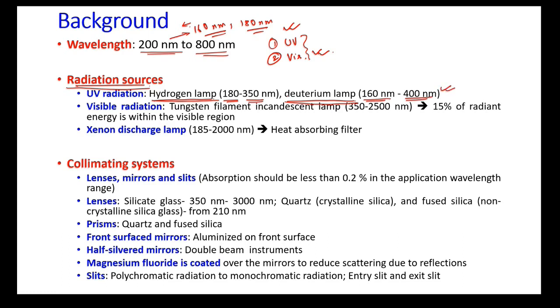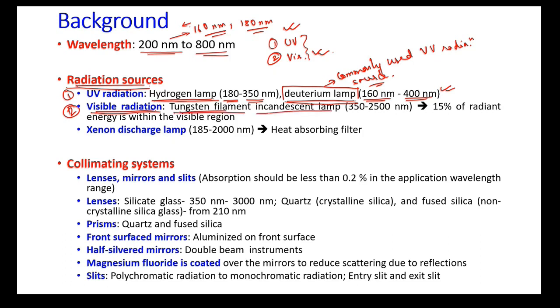In current-day UV-visible spectroscopes, the deuterium lamp is the most commonly used UV radiation source. For the visible radiation source, we usually use a tungsten filament incandescent lamp, which generates radiations in the range of 350 to 2500 nanometers. However, visible spectroscopy works up to 800 nanometers, because beyond that we are in the infrared region.